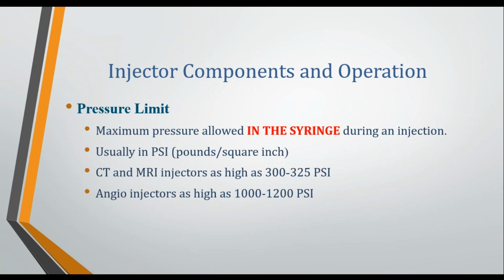Now, the pressure limit is the maximum pressure allowed, and this is the sometimes misunderstood part. This is the maximum pressure allowed in the syringe during an actual injection. When we're performing an injection, you have your syringe, and then you have that thin connector tubing you saw me connect earlier in one of the videos. Let's say we programmed a pressure limit of 1,000 psi. What that means is during this coming injection, we do not want the pressure in the syringe to exceed 1,000 psi. And again, the important part there is in the syringe.